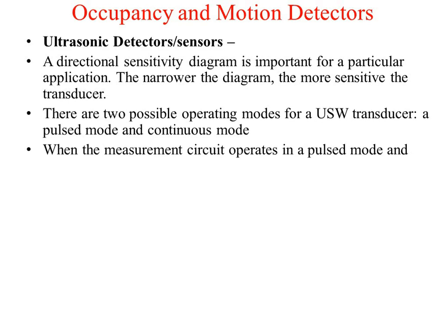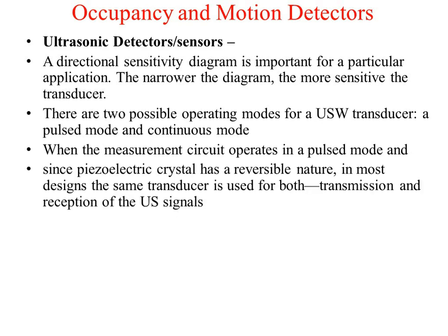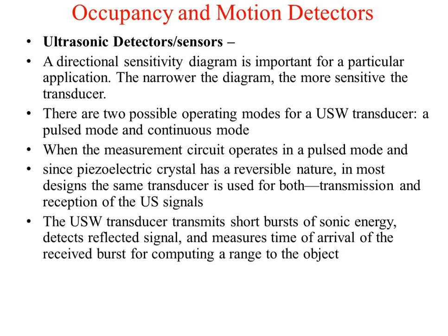When the measurement circuit operates in a pulse mode and the piezoelectric crystal is reversible in nature, in most of the designs the same transducer is used for both transmission as well as the reception of the ultrasonic signal. US here means not United States, it is an ultrasonic signal. Then it is called a pulse mode, and if it is in continuous mode, most of the time the transmitter is different and the receiver is different.